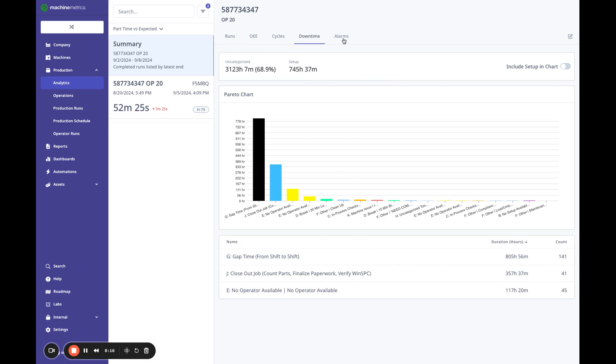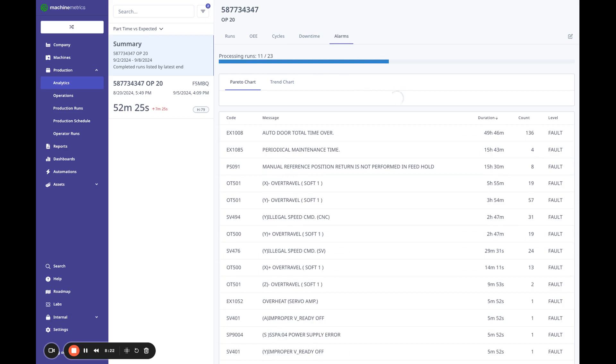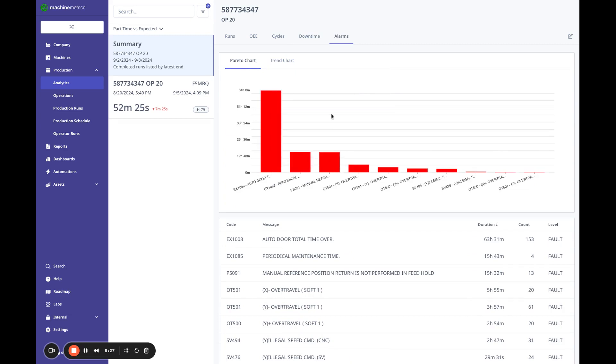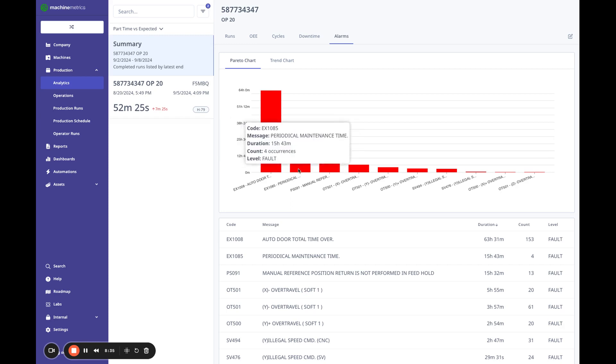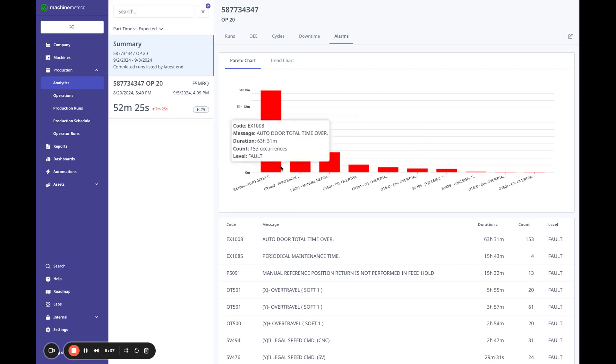But also we have alarms and what this does is this is going to accumulate all the alarms from all the runs and give you that Pareto chart. So you can really see where, I've got this auto door total time over, this is causing 63 hours of downtime. So this really is where I should be looking to try to help my availability here.